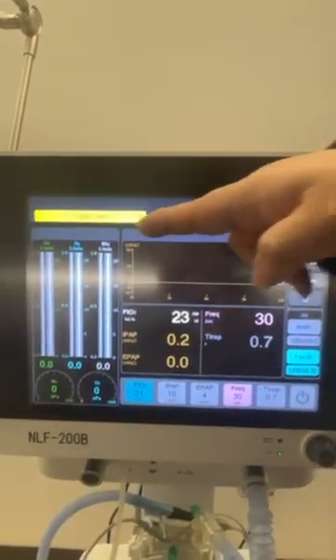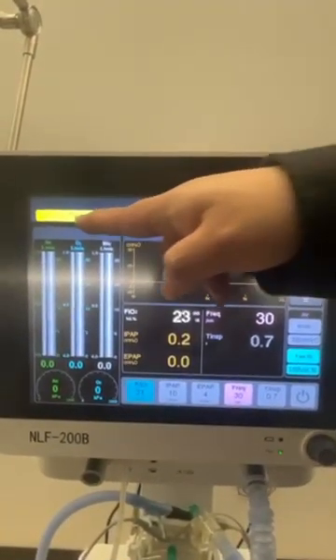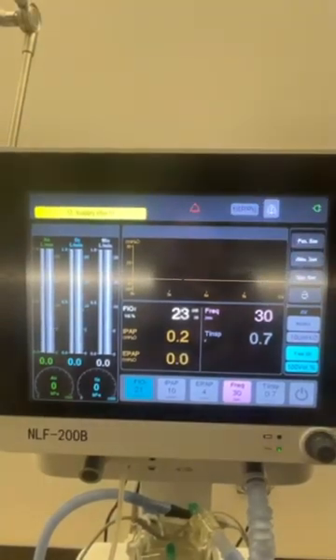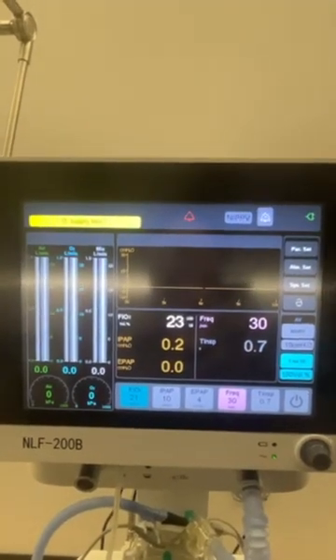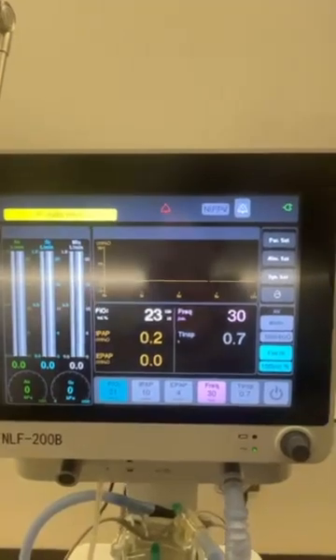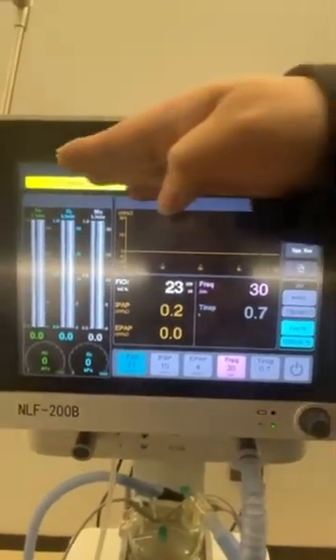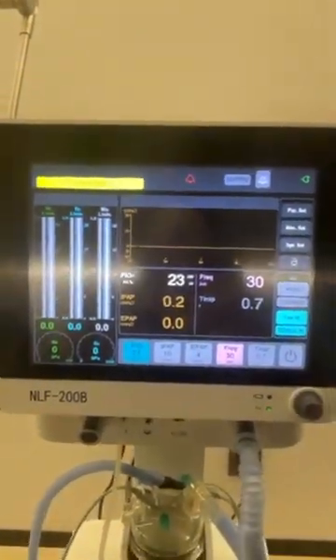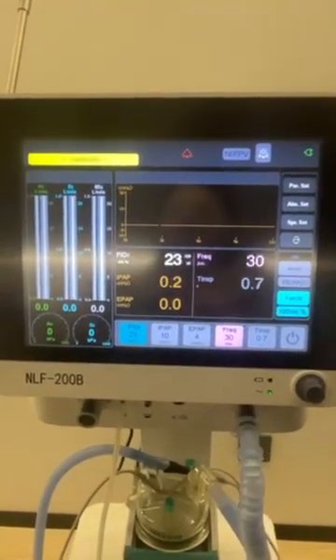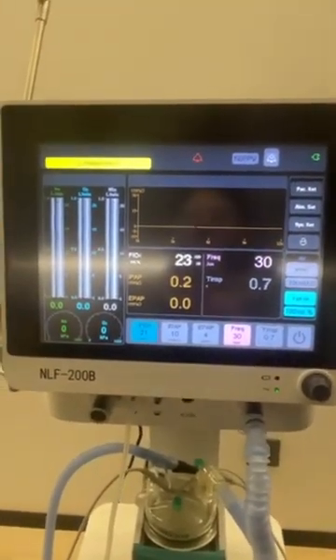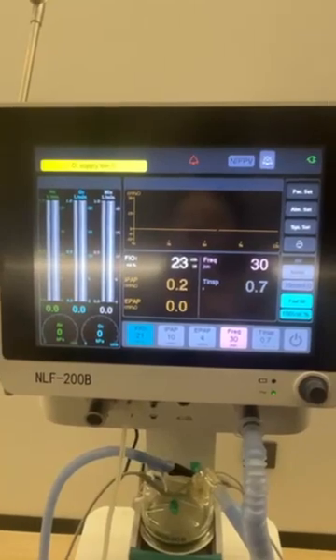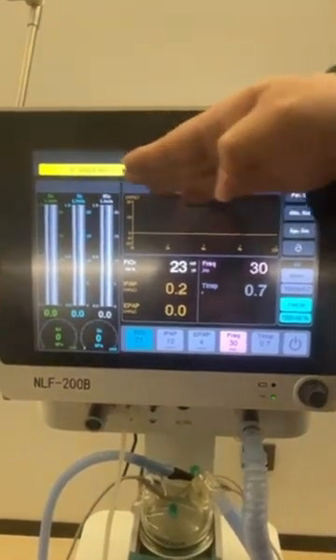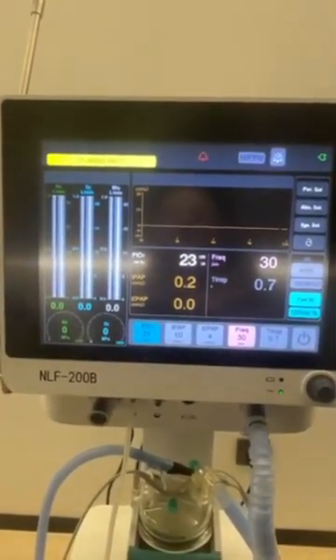So you can see different colors of the alarms. Now it shows the yellow color, and we also have another kind, the red color. The red color means the first level, and the yellow color means the second level. If it comes with the red color, then the machine, of course, cannot be used. So you must check the situation first, maybe the connections or maybe some leakage. And if it's the yellow color, we will see what kind of alarm it is.